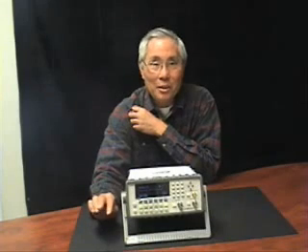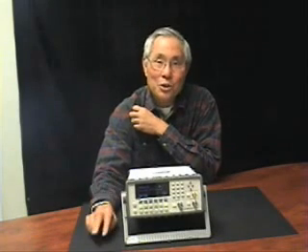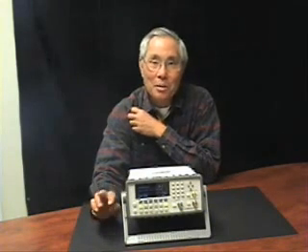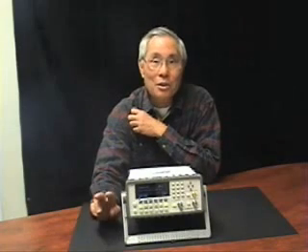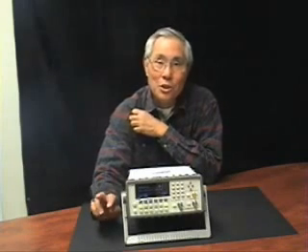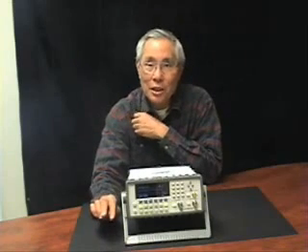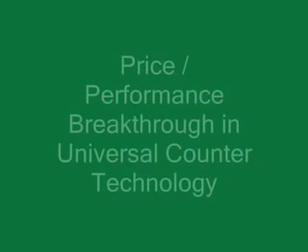We're excited because this unit breaks the price barrier. It is much less than $2,000, and for that you get 12 digits resolution in frequency and 40 picoseconds resolution in time interval counting.